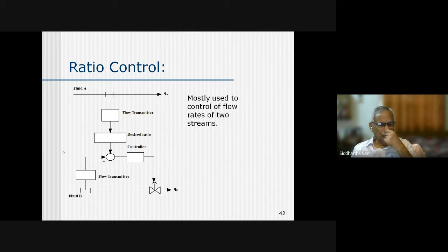We have a flow transmitter for fluid A, say fuel, and we want a desired ratio between the fuel and air flow. Fluid B is the air; I pass it and measure the flow transmitter. Accordingly, it should have this much flow, and I try to measure the actual flow rate. If it doesn't match, the controller operates the control valve to adjust the air flow rate.